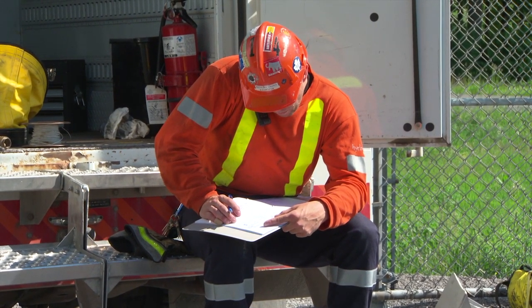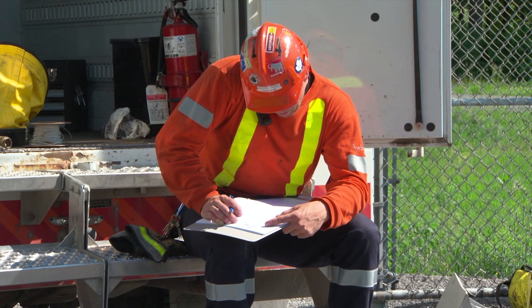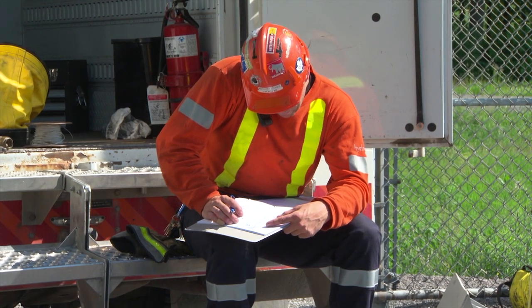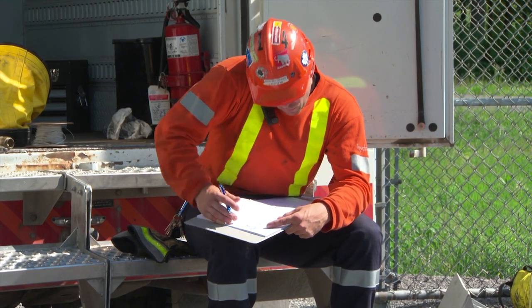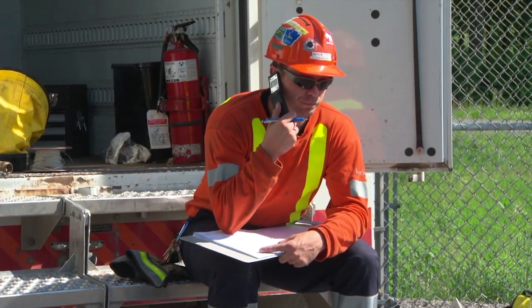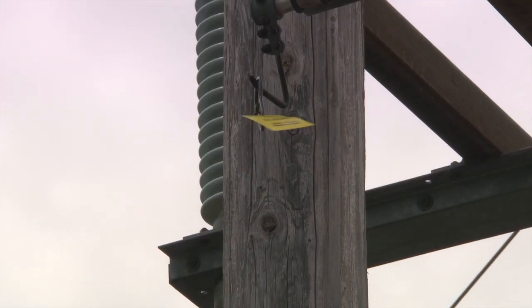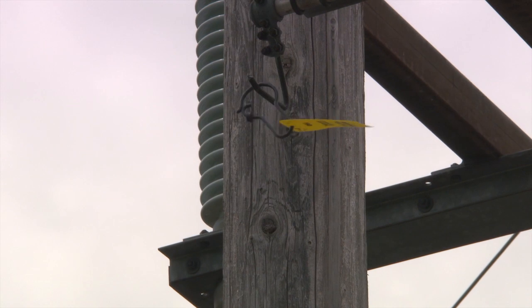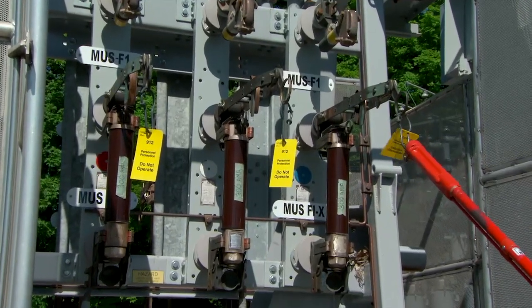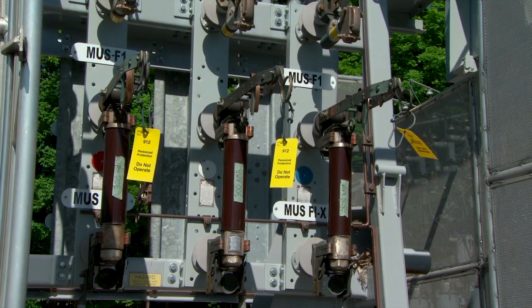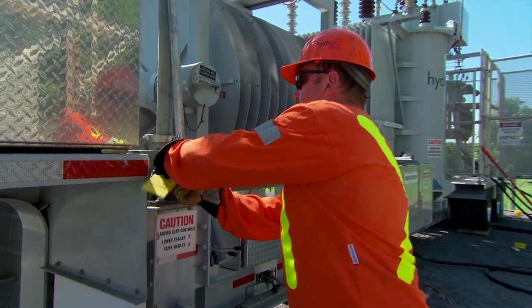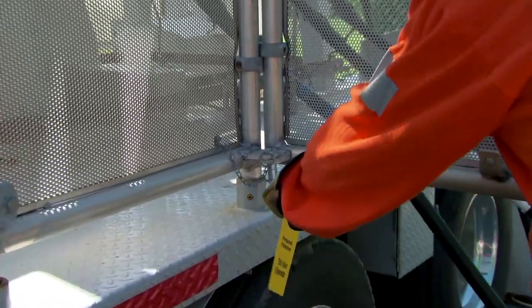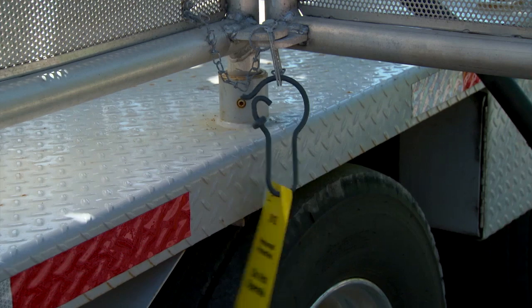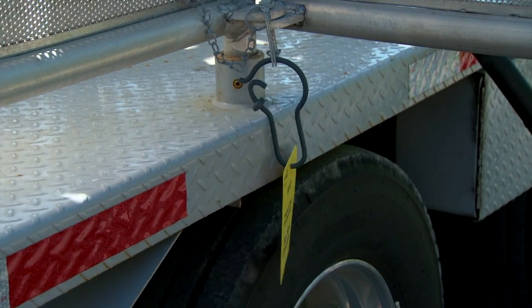You must now establish a self-administered work permit to connect the primary and secondary cables to the DS. This will require the LC-MUS loops opened and tagged, the low-voltage MUS feeder switches opened and tagged, and the high-voltage switch opened and tagged. Some crews also choose to control the position of the feeder gates with work protection tags.